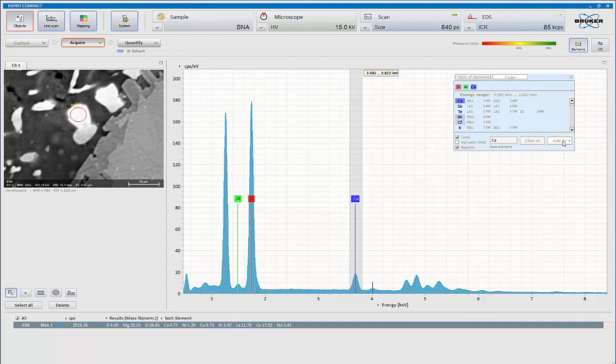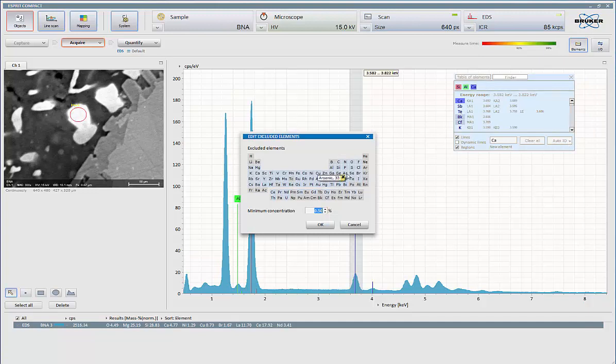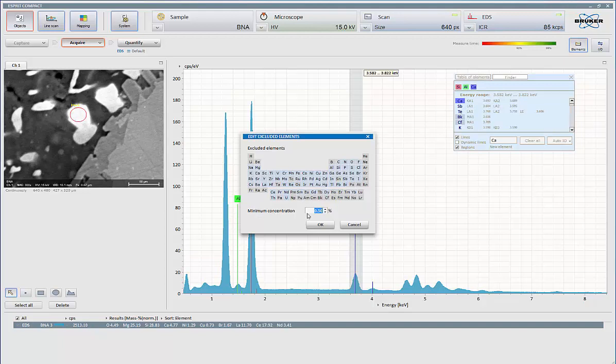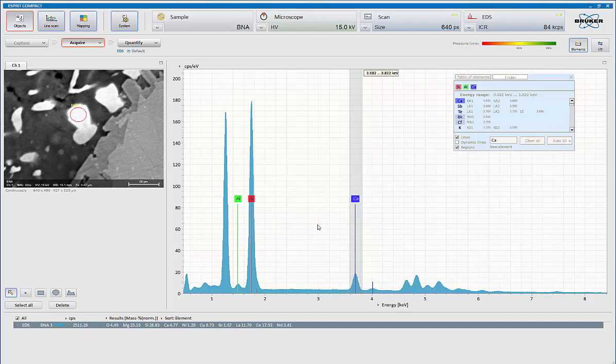Or I can utilize the auto ID function. With auto ID, there's a down arrow key, which means there's a menu. So I can set elements I know I'm never going to see. So anything that's gray means don't consider it. So if I don't want, I know I'm never going to use osmium in any of my analysis, I can simply click on it and that tells the system, don't even consider it, I never see it. Anything that's blue means consider. So if I wanted osmium in, I just click on it again. So it's just a simple toggle. I can also set minimum concentration. So typically I like to do this for the trace element. So I will usually set this somewhere between .25 and 1.5% and let the system do all the majors for me. OK, it closes down that panel.